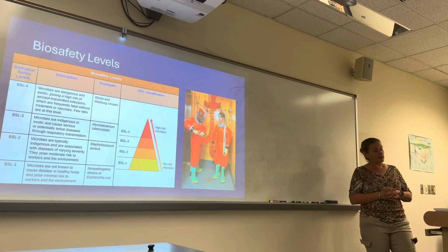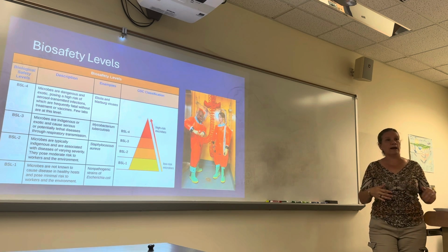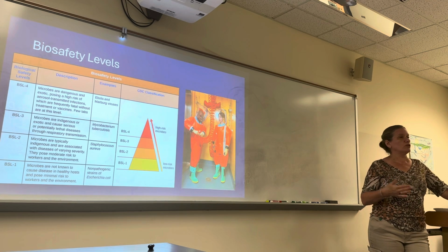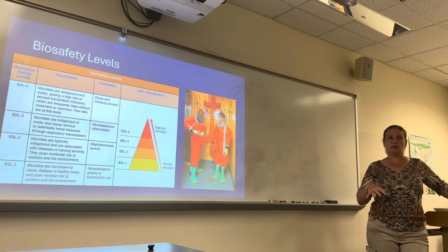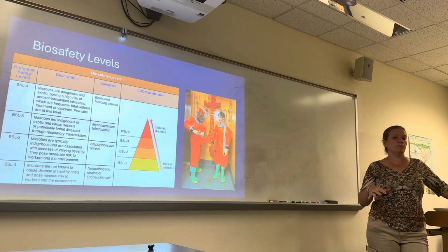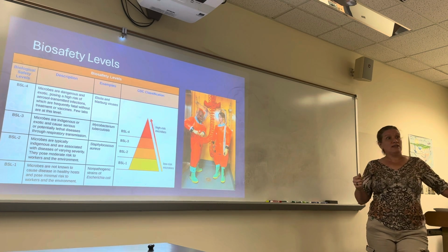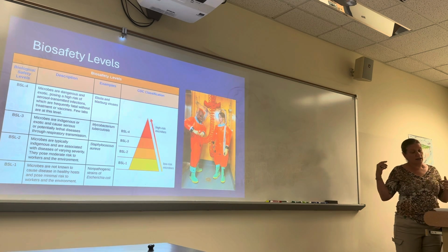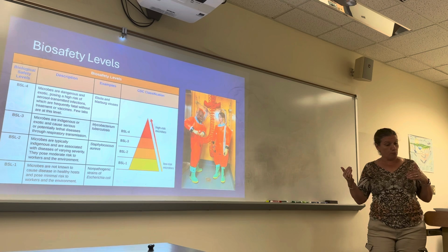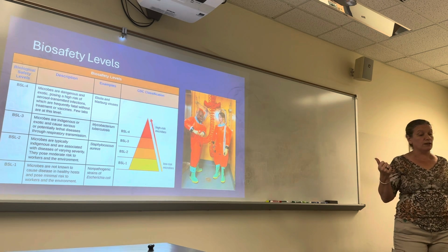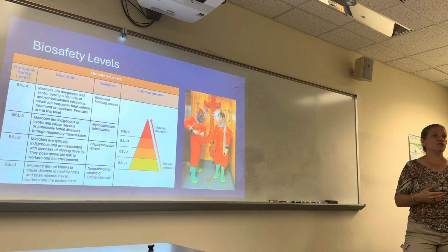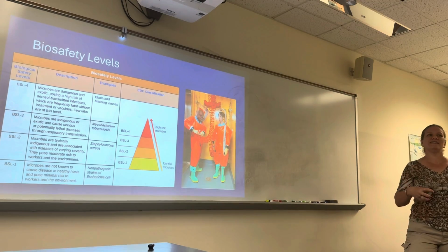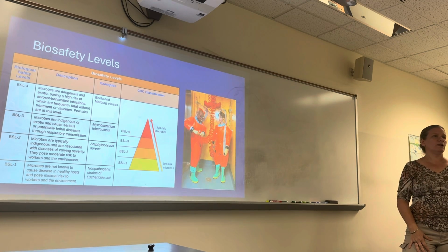And we'll talk about that actually in this module with the biosafety cabinets. You've got UV light that prior to use and right after you're exposing that biosafety cabinet with UV light to disinfect the workspace and the air in the workspace, and then any air being drawn in and any air leaving, both coming in and before leaving, that air is going through HEPA filters to remove any bacteria. So again, to contain any organisms in that biosafety cabinet, right?